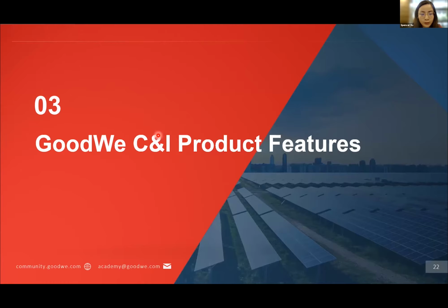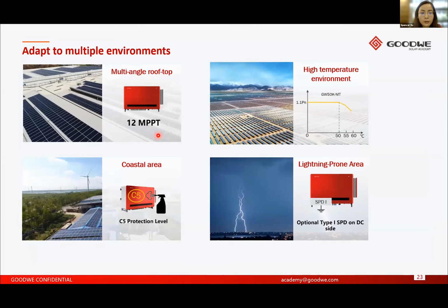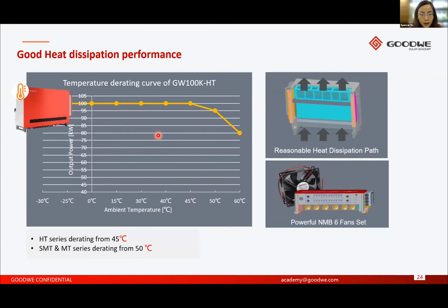Next, let's have a look at GoodWe's product features. GoodWe inverters can adapt to multiple environments. For example, for multiple angle rooftops, we have up to 12 MPPTs, so it is very flexible for the system design. GoodWe inverters also feature full load operation at high temperature and can also adapt to the coastal area because the HT series have the C5 protection level. For lightning-prone areas, an integrated Type 1 SPD on the DC side is also available to be chosen. In high temperature areas such as Southeast Asia, GoodWe inverters can still have excellent performance because we can keep the full load at 50 degrees for SMT and MT models. And for the HT series, it won't derate until 45 degrees.